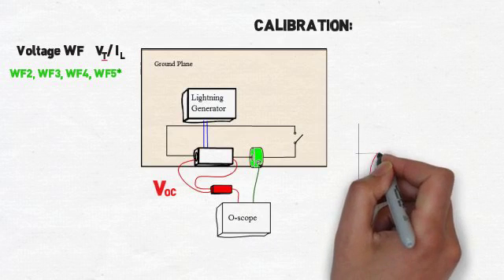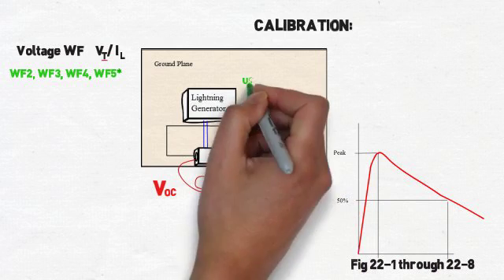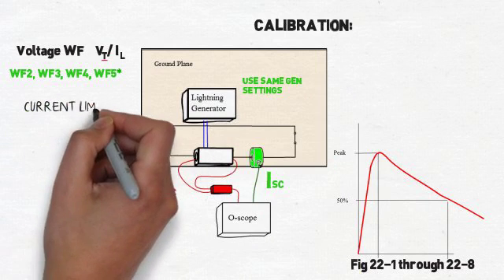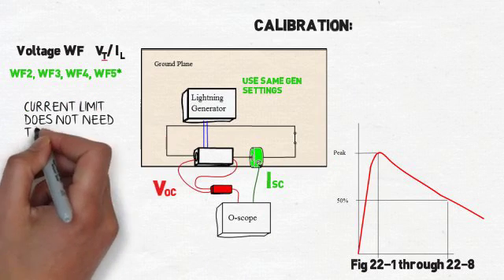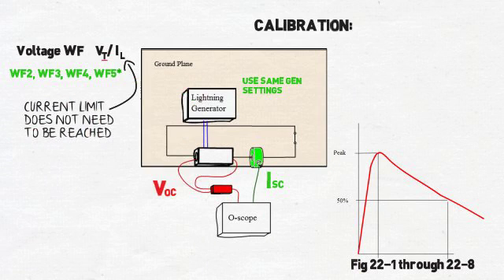We'll also need to ensure that the voltage waveform and the timing requirements match the waveform shown in figures 22.1 through 22.8. After achieving voltage with the loop in the open circuit configuration, the loop should be closed to test the short circuit configuration. The generator should be set to the same test level that achieved voltage limit. The current seen during this test does not need to reach the current limit, but is merely an indicator of how much power your transient generator and clamp is delivering.